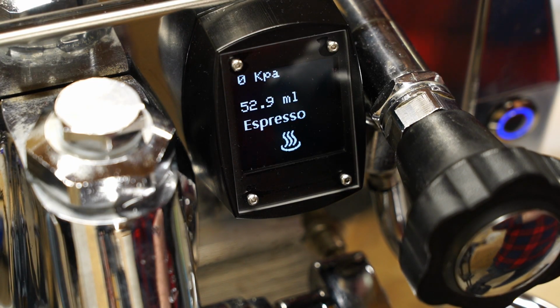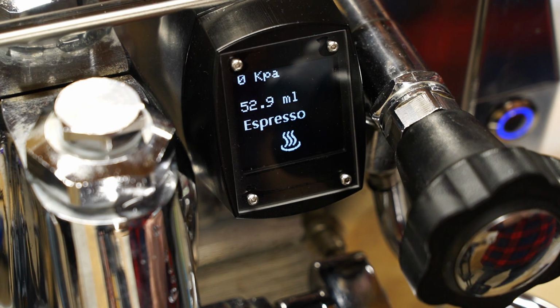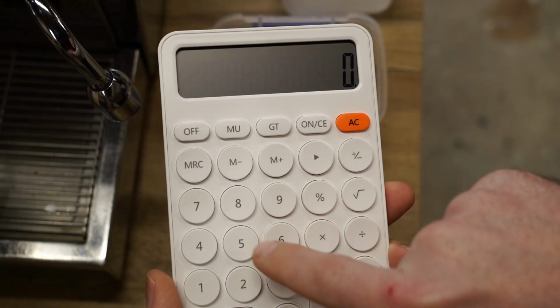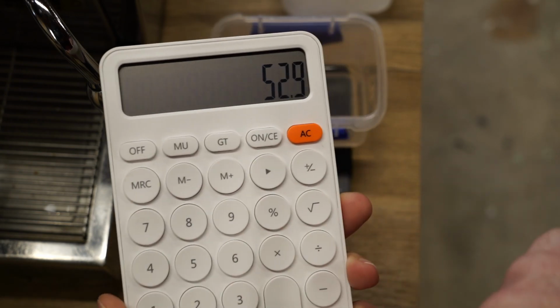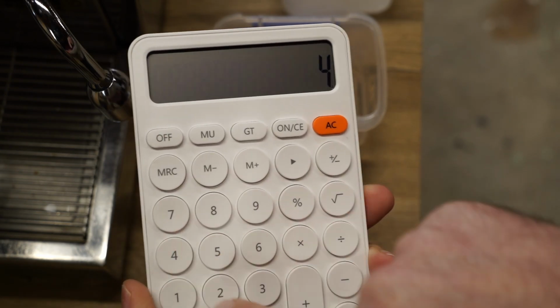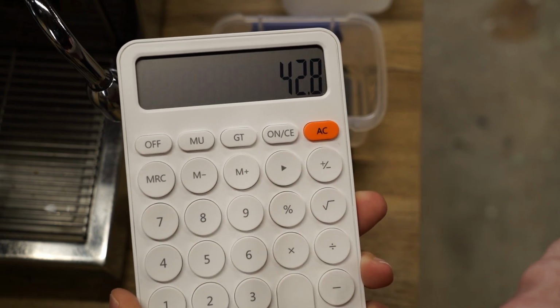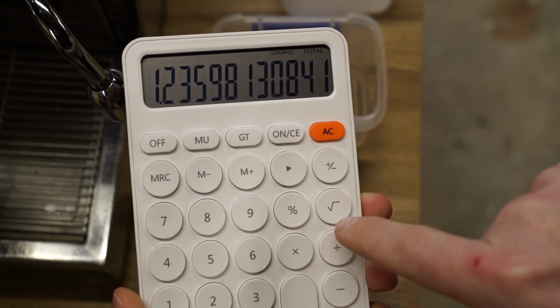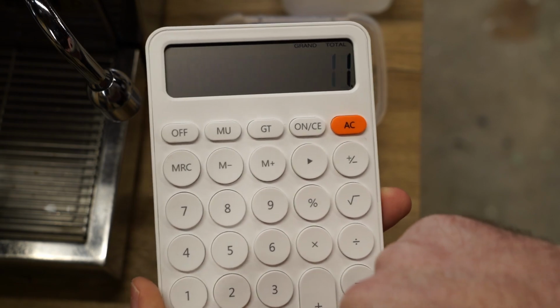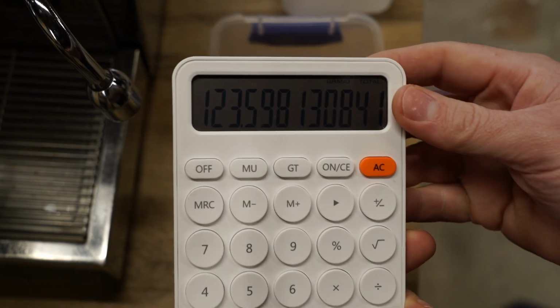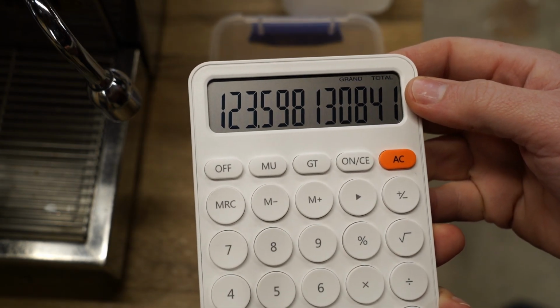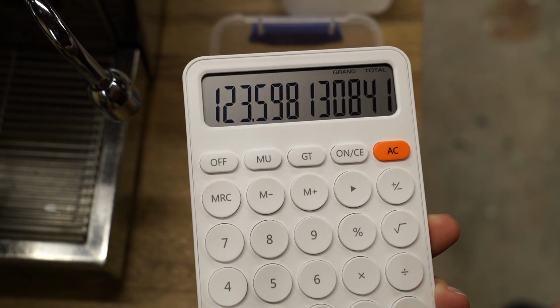Just like before, I noted down the displayed water volume and then weighed the water. Then it's simply a matter of dividing the displayed water amount by the actual amount of water and then multiplying that by my current pulses per mil value. My new pulses per mil value is 123.6.